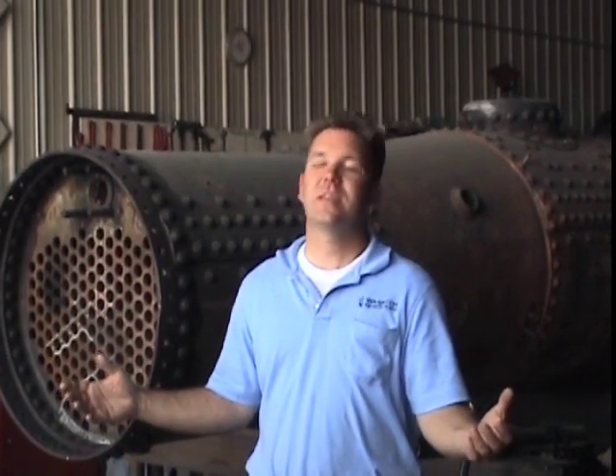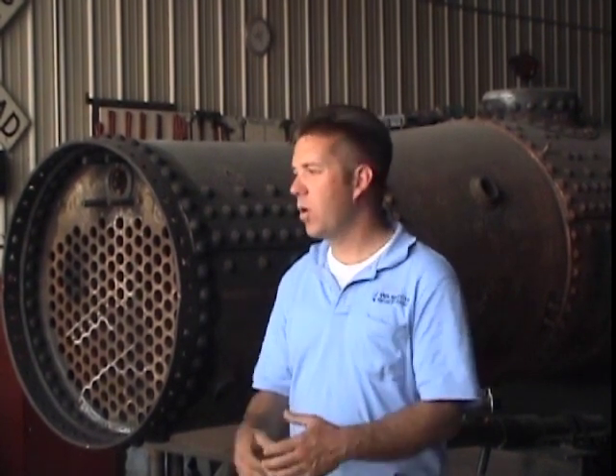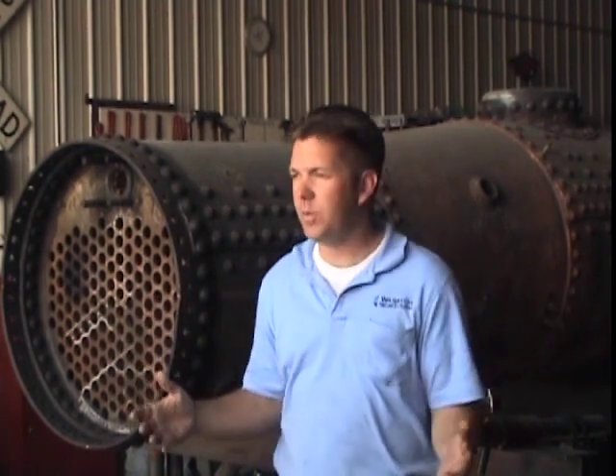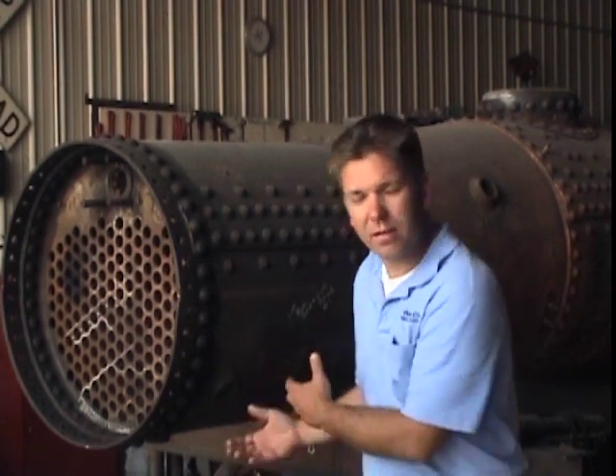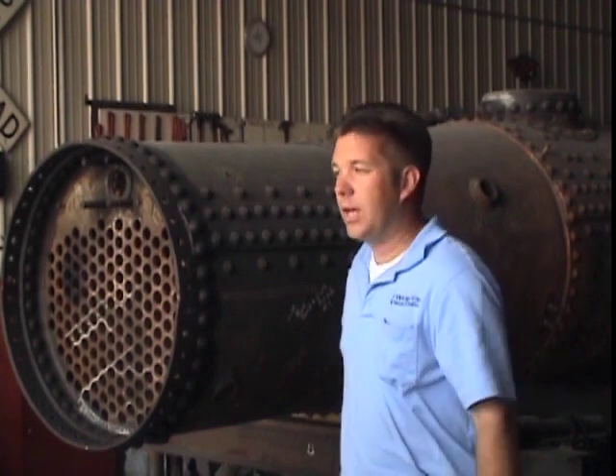A common question these days is: why is this ASME code thing so important? The reason it's become so important is because nearly all of the states within the United States of America have adopted the ASME code as the formal code of construction for new pressure vessels. As such, the states are generally requiring that locomotive boilers or pressure vessels in general that are operated within public spaces — be that an amusement park or even private property where the public has access — the states have the ability and the right to come in and ask: what's this pressure vessel you're running? Who built it? When was it built? To what standard was it built?